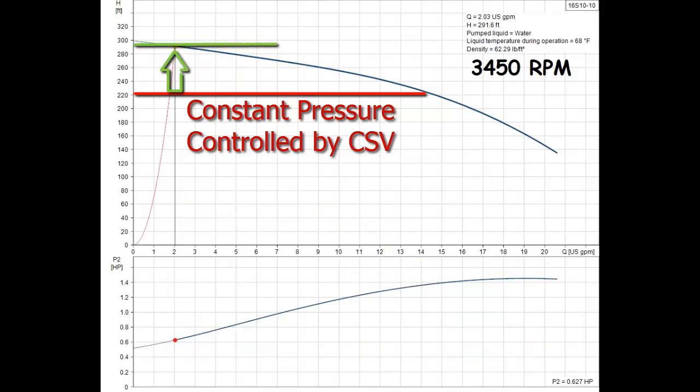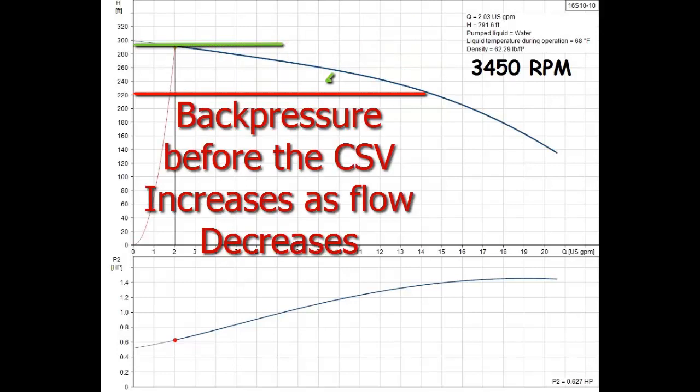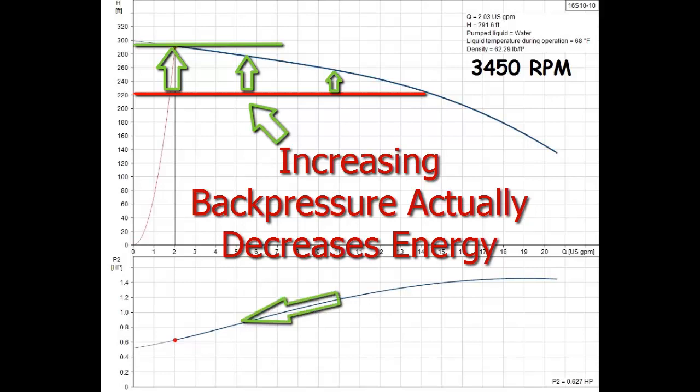The CSV makes the pump think it is in a deeper well, so it produces less flow when needed. The pressure before the CSV, which is called back pressure, increases when the flow is reduced. We now know that increasing the back pressure of the pump actually decreases the horsepower and makes the pump work easier.